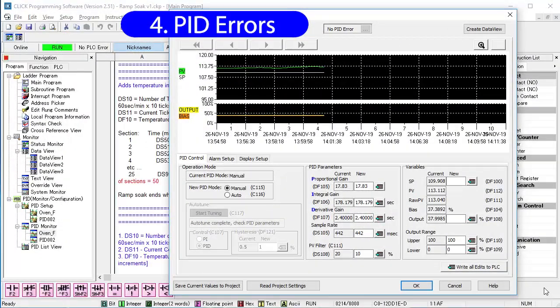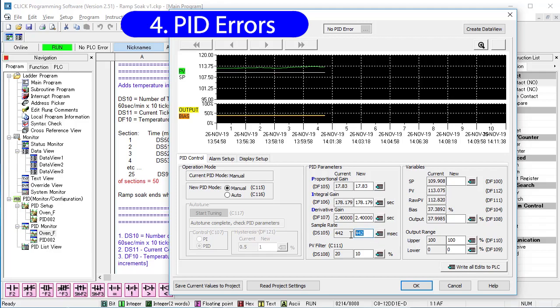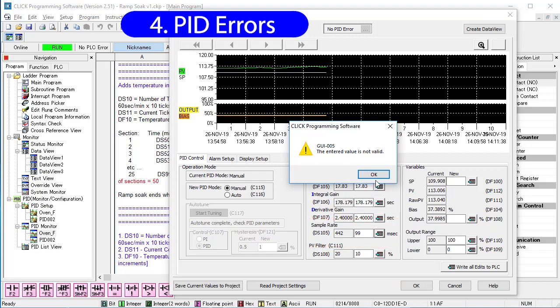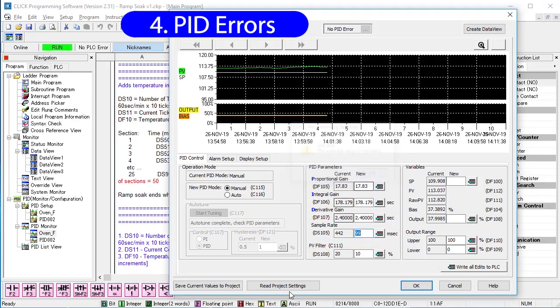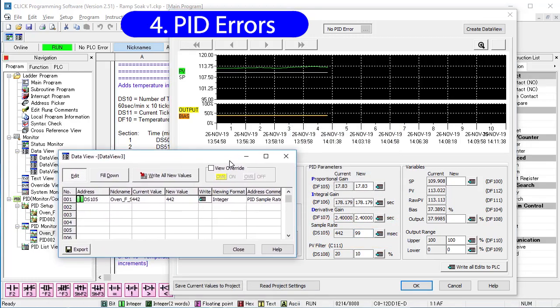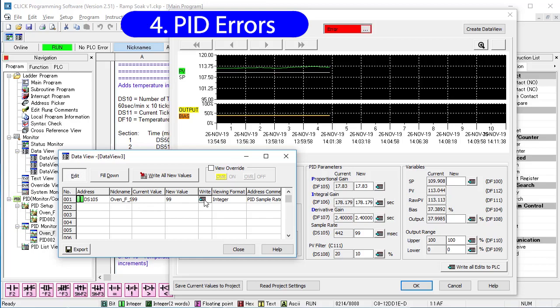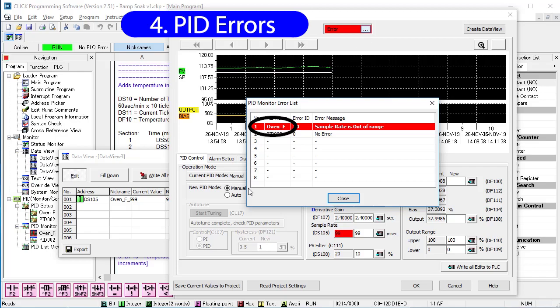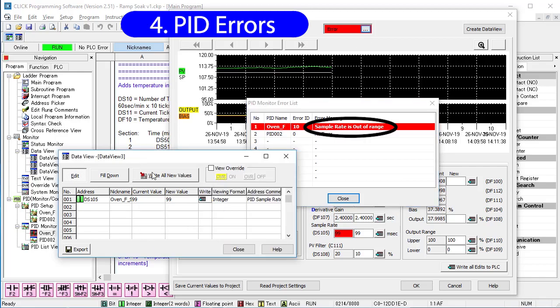Speaking of errors, the PID dialogs are really good about error checking. For example, if I try to enter something below 100 ms for the sample time, I get an error. But you can also write to this from ladder or even a data view where you may not have error checking. The good news is the Click PID watches your back and tells you if you did something wrong. Open this error dialog and you see that this PID loop has this error. Fix it and the error goes away.